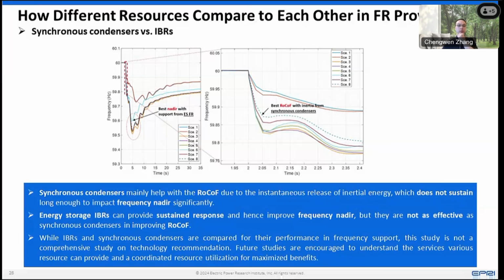The key takeaway here is that synchronous condensers mainly help with RoCoF due to their built-in inertia—they're very effective at that. But if you look at the frequency nadir with synchronous condensers, it almost doesn't change, because the release of energy from them isn't sustainable. It's only in the first few moments, when frequency declines very fast, that the inertial energy is released. Past that, there's no sustained release, so the frequency nadir doesn't change.